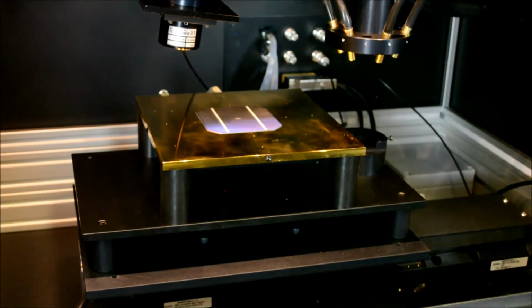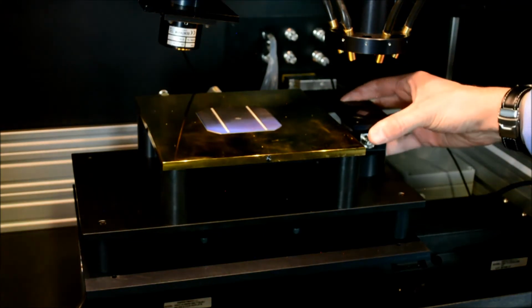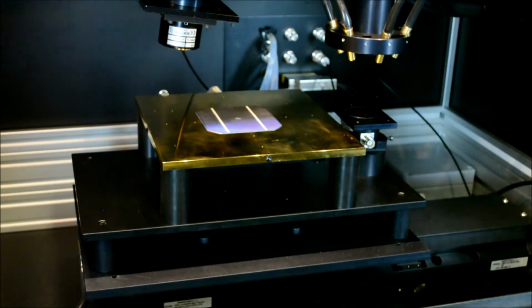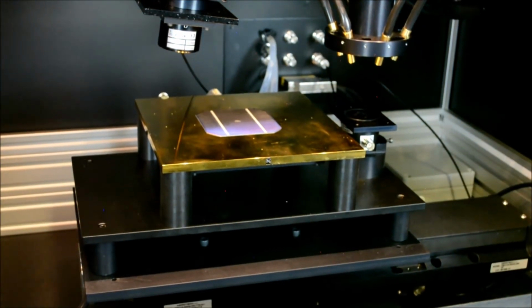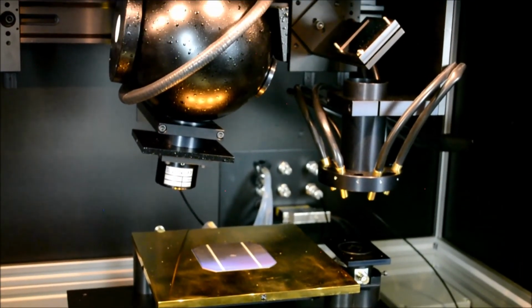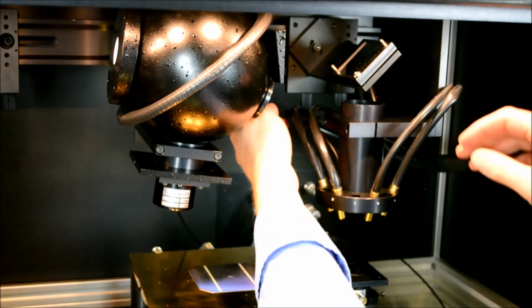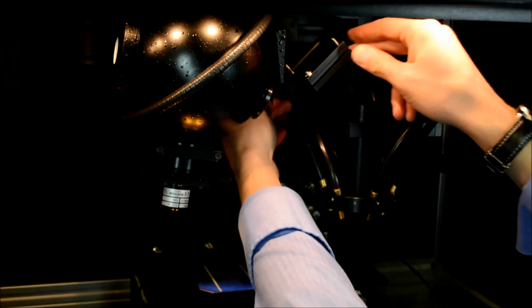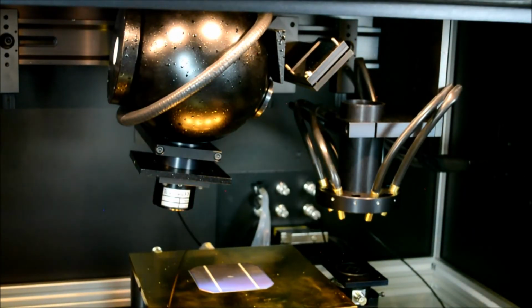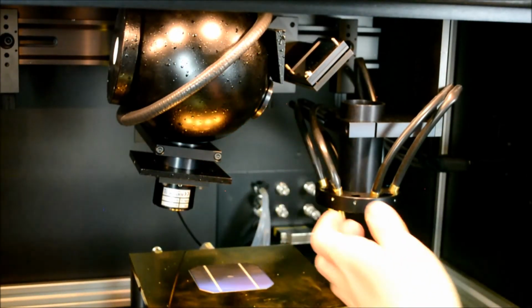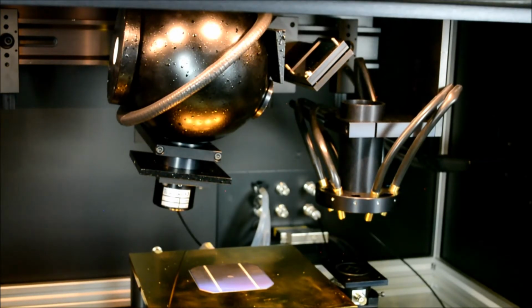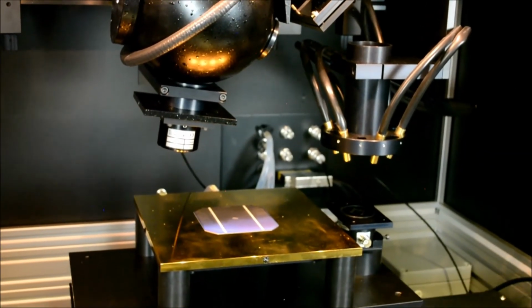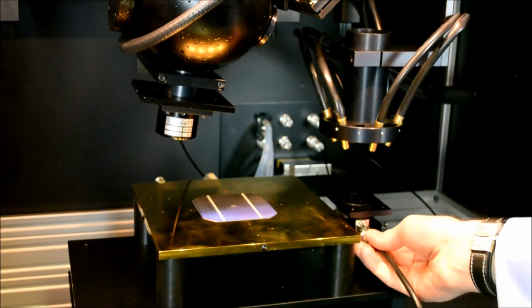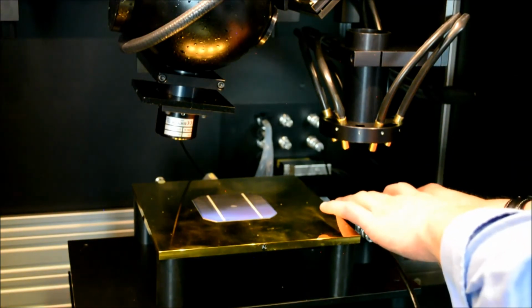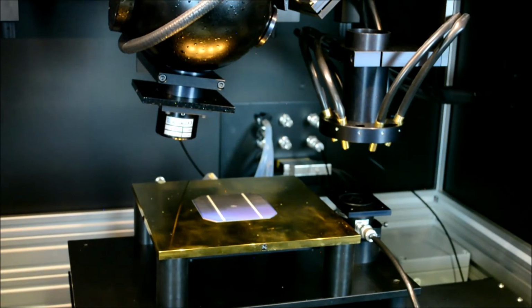So we have now to place the reference diode under the beam of the PV300. We must also make sure that the divert mirror at the top of the PV300 chamber here is moved to the left position, thereby allowing light to transmit to the temperature controlled vacuum mount and reference diode. One simply turns the thumb screw by a quarter of a turn to translate across, and then fixes it back in place. We can connect the reference diode to the transformer using the thick BNC cable provided, and of course we should fix the thumb screw to the side of the detector to hold it in place.